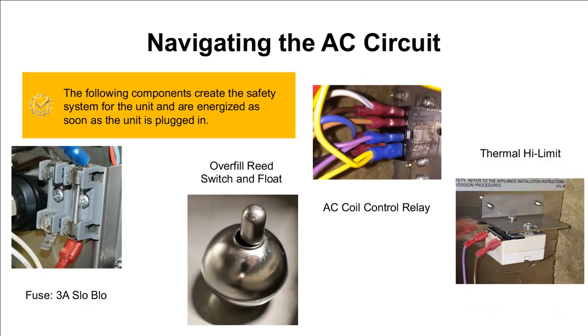So, first thing I'd like to talk about are the safety components. That comprises our single 3-amp slow blow fuse, an overfill reed and float that is only available on the autofill, it is not needed on the manual, the AC coil control relay or control relay 1, and the thermal high limit switch. Now, as a quick update, we did recently update the thermal limit switch. That was phased in in April of this year, and it is not backwards compatible. If you'd like more information on that, we can answer any questions at the end of the slide.